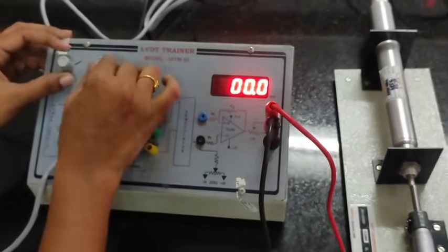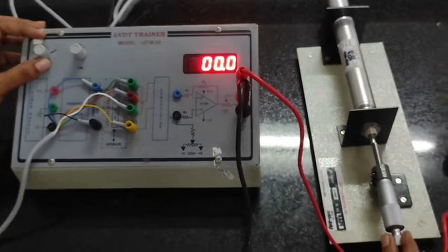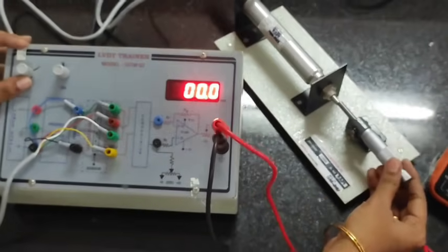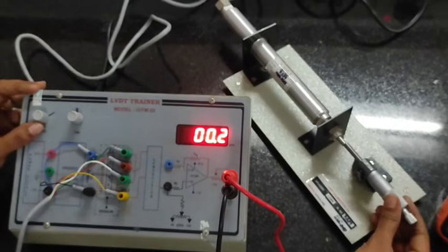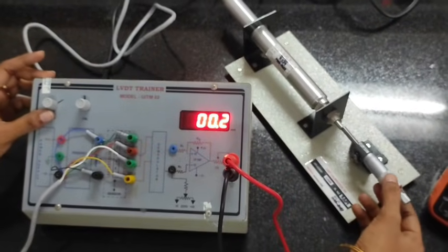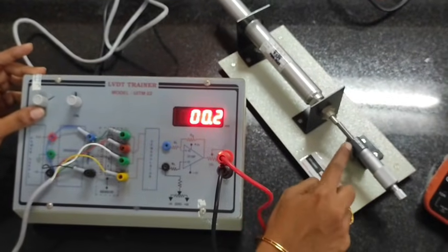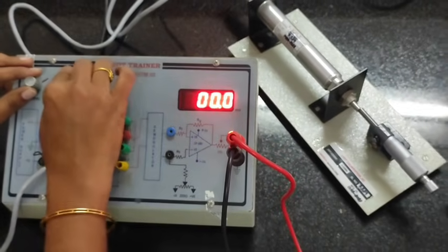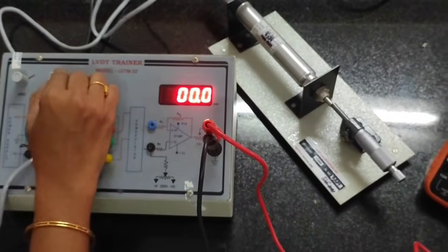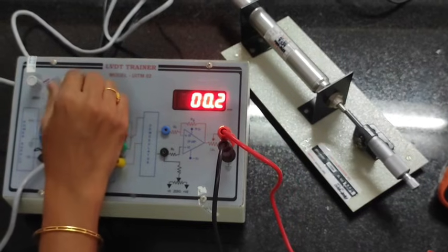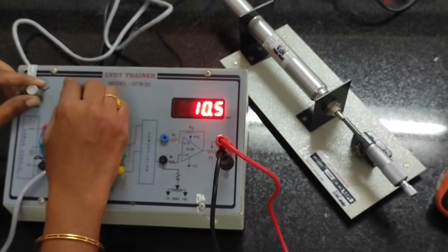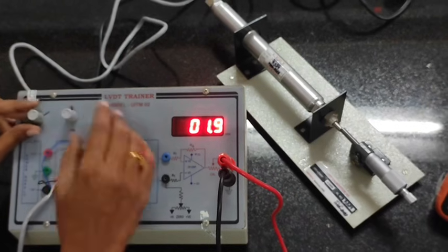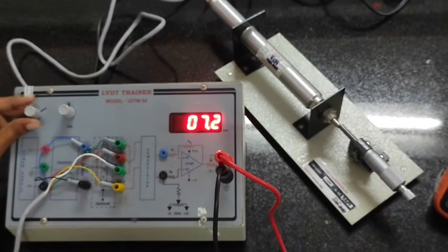Next step is calibration. There are span adjustment and zero adjustment. In the screw gauge, we are keeping the center position as 10. There are inner side scale readings in this screw gauge. By making this span adjustment and zero adjustment, we are making zero for the position 10. We have to make zero for 10.